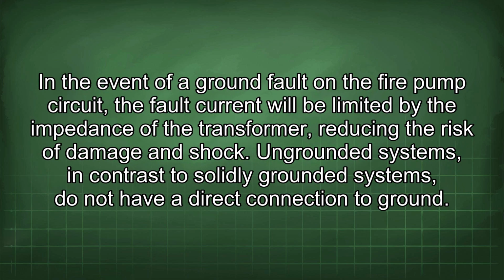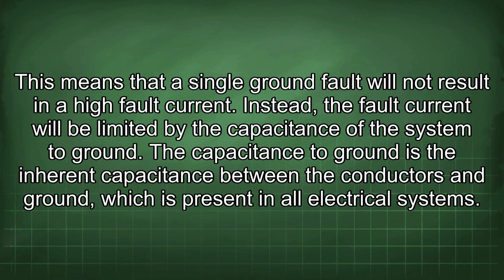In the event of a ground fault on the fire pump circuit, the fault current will be limited by the impedance of the transformer, reducing the risk of damage and shock. Ungrounded systems, in contrast to solidly grounded systems, do not have a direct connection to ground. This means that a single ground fault will not result in a high fault current. Instead, the fault current will be limited by the capacitance of the system to ground. The capacitance to ground is the inherent capacitance between the conductors and ground, which is present in all electrical systems.